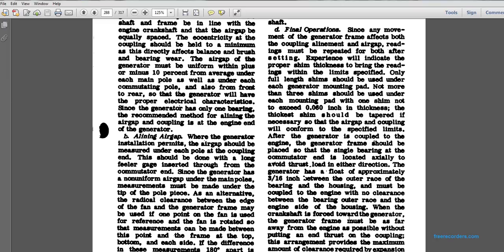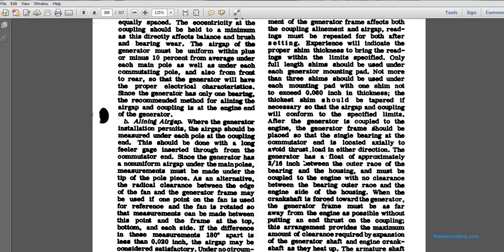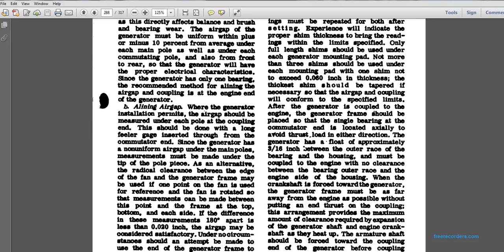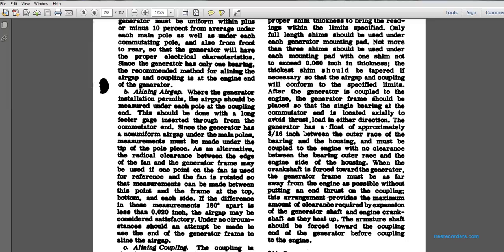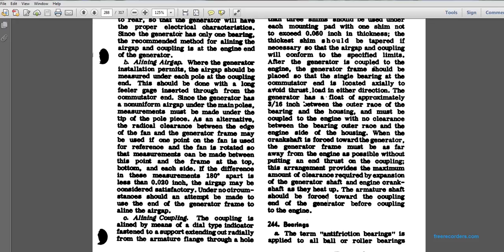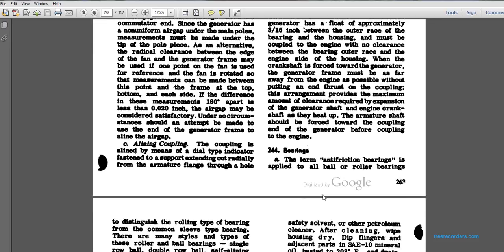When the crankshaft is forced toward the generator, the generator frame must be as far away from the engine as possible without putting any end thrust on the coupling. This arrangement provides the maximum amount of clearance required by expansion of the generator shaft and crankshaft as they heat up. The armature shaft should be forced toward the coupling end of the generator before coupling to the end of the engine.